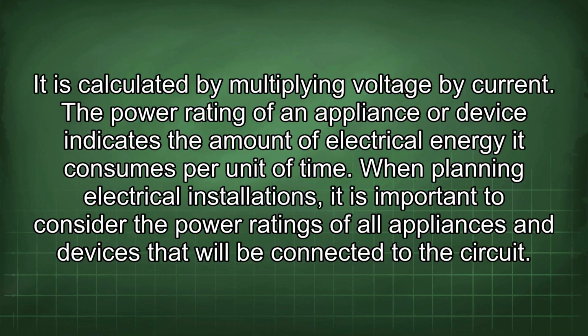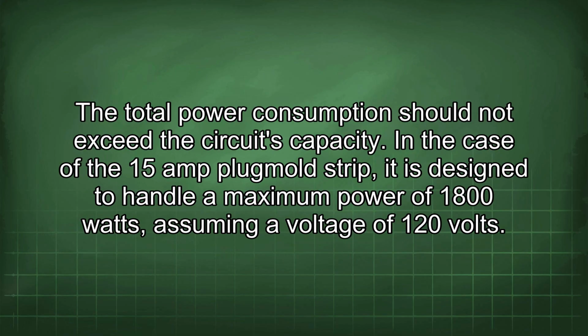The power rating of an appliance or device indicates the amount of electrical energy it consumes per unit of time. When planning electrical installations, it is important to consider the power ratings of all appliances and devices that will be connected to the circuit. The total power consumption should not exceed the circuit's capacity. In the case of the 15-amp Plugmold strip, it is designed to handle a maximum power of 1800 watts, assuming a voltage of 120 volts.